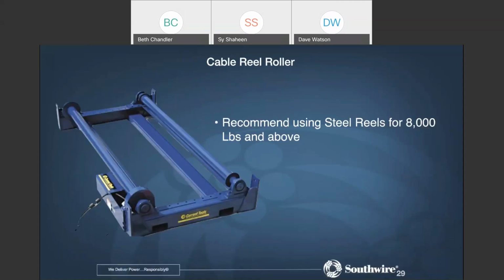Again, through my experience, almost every job site uses this. And while it's a very good piece of equipment, I'm not here to say it's bad or anything, but it has its quirkiness. This is what's called a bed roller. You put the reel on here, and these shafts turn, and as they turn the reel, you can feed the reel that way. The problem with this, when you use really heavy reels, I mean wooden reels, is that wooden reels are not meant to take this much abuse, because this reel is turning maybe 50, 80, 150 turns.